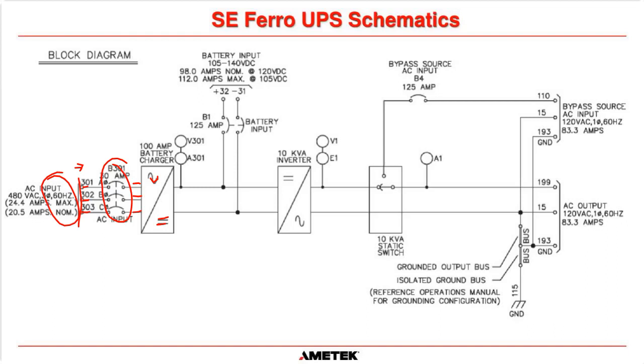Okay. And then on the output there, we have V301, which is a voltmeter, and A301, which is a DC ammeter. So we can tell whether the battery is charging, discharging, how much current is flowing on the DC bus, and what the voltage of that DC bus is. And they are analog meters on this system. And then you can see here that we then parallel off to the battery, and we have a battery input breaker, which is labeled B1.